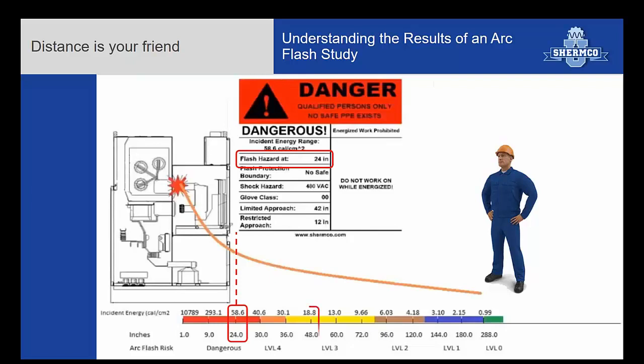If we move a little bit away, if we double our distance, say to 48 inches, it drops down to 18.8 calories, which is almost a quarter of the original 58. So if you double your distance, your calories go down by the square of that distance, roughly. It's not exact. But distance is so important, and you have to realize every study is done at a distance, and then whatever task you're doing, the worker has to decide, is that distance where I'm going to be?